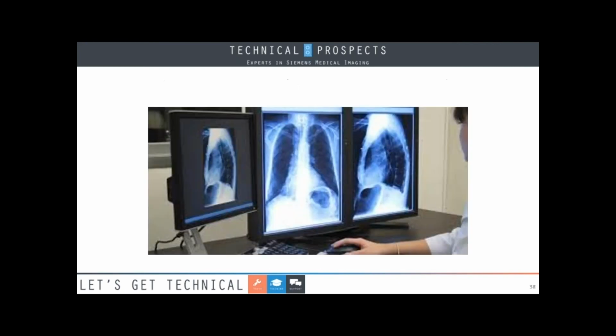Now here's a little bit of a more delicate issue, image quality issues, okay? If they're complaining about the image on the monitor, that's the time to calibrate. Okay, that's a good time to say, okay, well, it looks garbage, I'm gonna calibrate it. I would ask them is the image consistent with this monitor and another one? Because chances are the operator's console is not the only one being used. Usually they send to a PACS system. Usually the physician's actually not even there. They're sitting in this dark room. It's kind of like a forbidden room. You don't even go near there. It's like kind of awakening a bear who's hibernating. So their monitor might look totally different. But at that time, if it doesn't work, absolutely calibrate it.